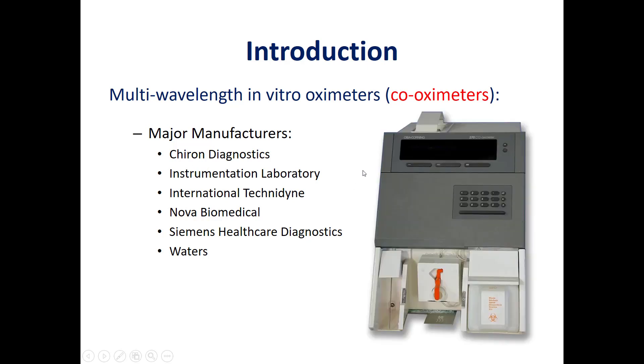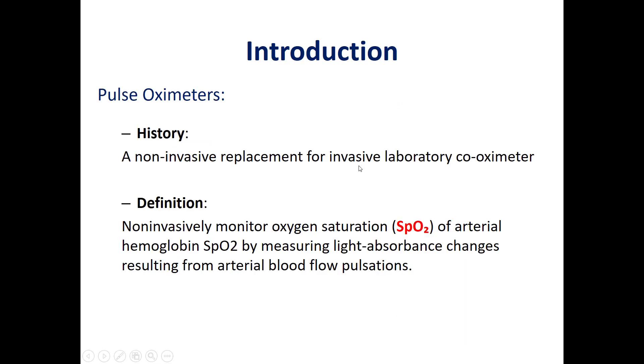This is an image of a commercial lab co-oximeter. Now we will start talking about the pulse oximeter, which is a non-invasive alternative or replacement for the lab co-oximeter, which is invasive and requires a blood sample. The pulse oximeter is a non-invasive device that measures or monitors the oxygen saturation of arterial hemoglobin by measuring the light absorbance changes resulting from the arterial blood flow pulsations.